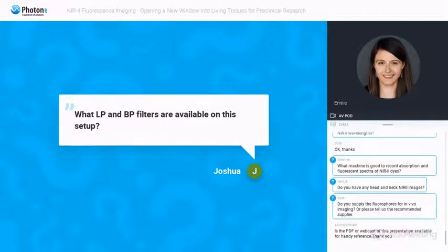So if the client already knows which probes he wants to image, and if we can determine the best filter for these, we can go with these filters. Sometimes we provide a few filters, and we keep some empty spaces in the filter wheel. So if the client wants to add his own filter and be able to change them, this is a possibility.